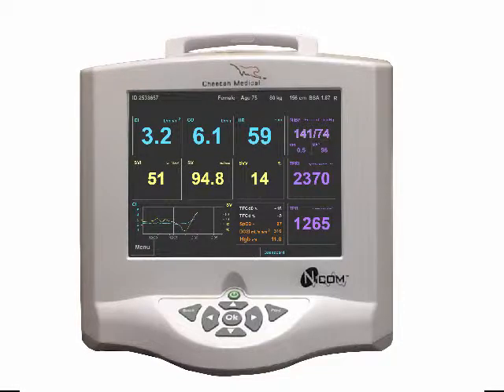The NICOM system uses a measured phase shift to derive the maximum aortic flow, and using the ventricular ejection time is able to calculate the stroke volume. The cardiac output is calculated by multiplying the stroke volume with the heart rate. Variability in the stroke volume measurements over time, SVV, is also reported and has been used as an indicator of whether or not a patient is fluid responsive. Stroke volume calculations are measured for every heartbeat, averaged over the minute, and updated every minute.